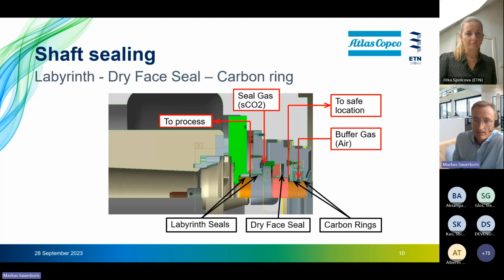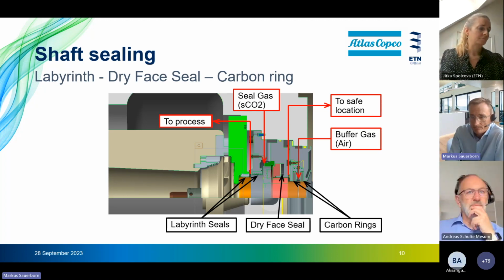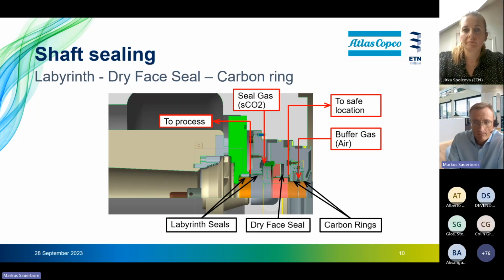Okay, come to the next. One of the design challenges is the shaft sealing system, which you can see here in this slide. This consists of a patented arrangement of labyrinth elements as a primary seal next to the impeller backside. The primary seal gas is taken from the compressor high pressure discharge side, which also protects the subsequent driver seal from high temperatures. The CO2 vent line is located between the labyrinth elements connected to the process low pressure side. And as a buffer gas to the oil side, air is used, which is injected at low pressure between the two carbon ring elements. The CO2 air mixture between the dry gas seal and the first carbon ring element is vented to a safe location.